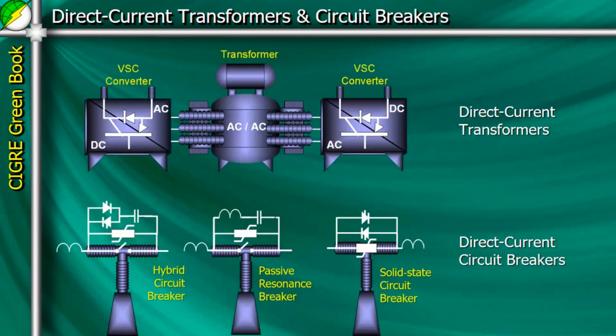Regarding these two challenges, the first is the development of direct current transformers, which is a major challenge for implementing the HVDC grid. One concept is to use two VSC converters together with a high frequency transformer to lower or raise the voltage in a DC grid.